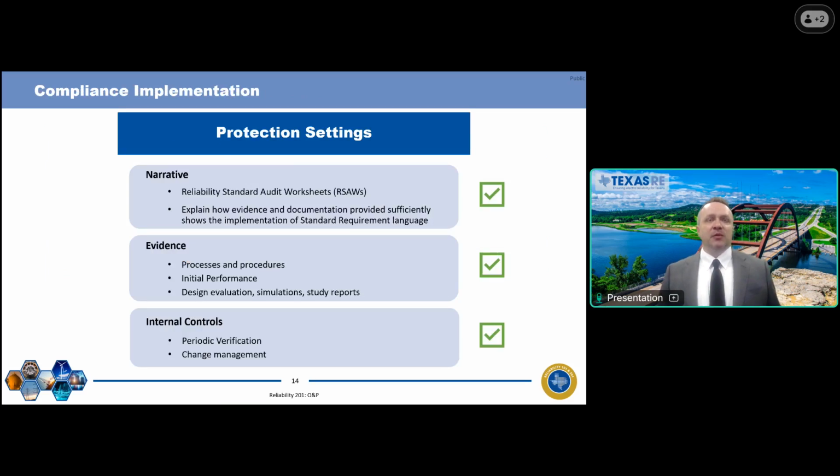So, compliance implementation. Again, we recommend following the RSAW, the Reliability Standard Audit Worksheet, and that will help you explain how the evidence and documentation that you're keeping will sufficiently show implementation of the different protection system standard requirements. I'm going to focus here on the PSMP, the Protection System Maintenance Program, because there are several failure modes associated with this program.